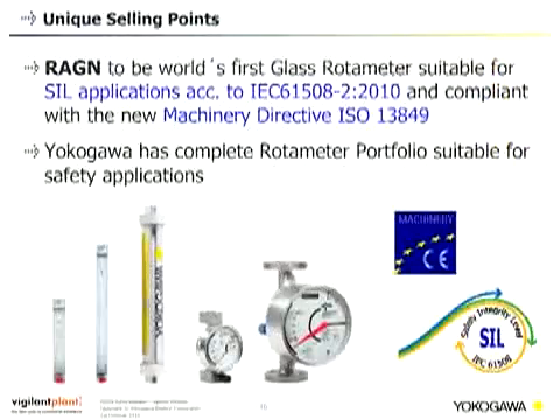The RAGN with limit switches is suitable for SIL applications. To summarize the unique selling points: the RAGN is the world's first glass rotameter suitable for SIL applications according to IEC 61508 and compliant with the machinery directive ISO 13849. Yokogawa is the only supplier in the variable area flow meter market with a complete portfolio suitable for safety applications. All rotameters with limit switches or 4 to 20 mA output signal come with SIL approval as standard — no special option required. Please refer to the safety manuals and instruction manuals for further information.